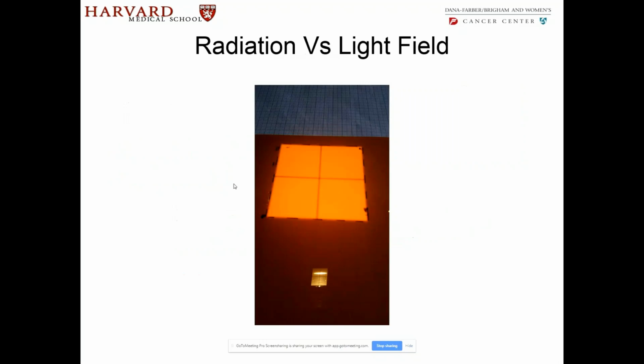The first thing, so there's a whole bunch of steps that we go through. I'll just show you some of the documentation to give you an idea of what it takes to accept a Linac. One thing was radiation versus light field. So when you go in and you say, okay, I open the jaws of the Linac to such and such an extent, and the light field says, okay, it's a 10 by 10 field, but when I irradiate it, how do I know it is exactly 10 by 10?